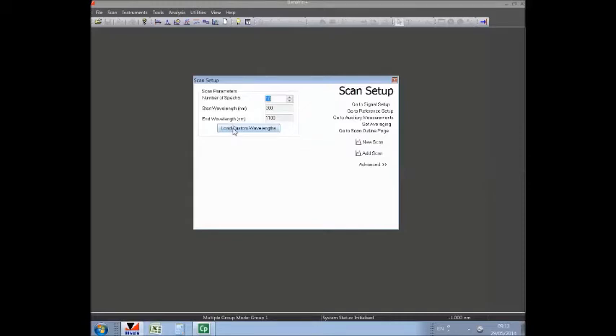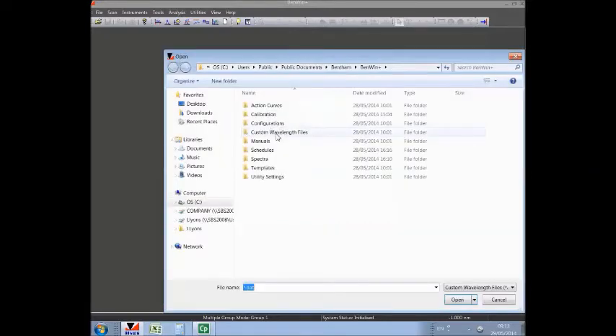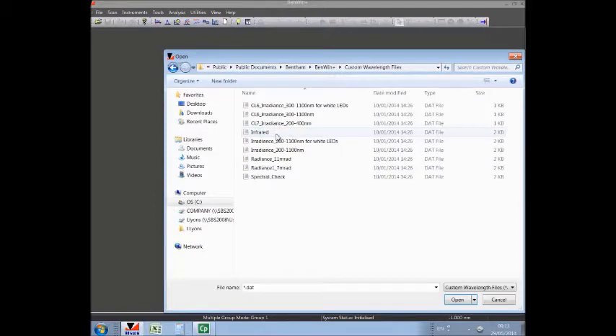Here we will use custom wavelength files to define the step size of the measurement. Normally, without custom wavelength files in place, the same step size would be used throughout the full start to end wavelength range. Here we would like to change the step size as we go through the scan range, and custom wavelength files are kept in this folder.